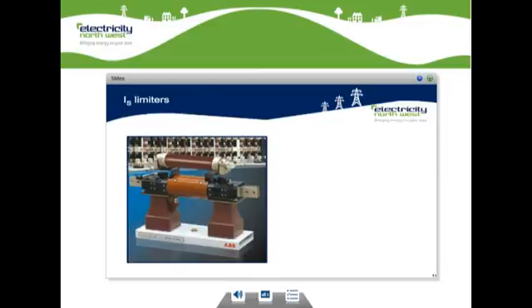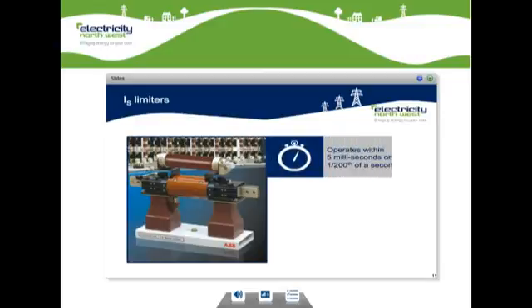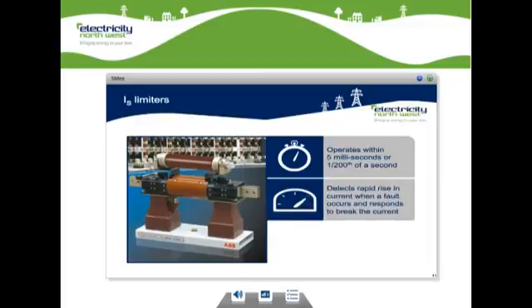Next, we'll cover the IS limiter. The IS limiter is a current limiting fuse. Now, our standard equipment will normally identify a fault and respond to it within a couple of hundred milliseconds. This might seem fast, but the fault current will have already peaked within this short time frame. An IS limiter, however, will operate within 5 milliseconds, or 1/200th of a second, before the fault current reaches its peak. When enabled by the Fault Level Assessment Tool, the limiter will monitor the normal current flowing through it. When a fault occurs, the limiter detects the rapid rise in current and responds by setting off a small explosive charge, which breaks or diverts the normal flow of current to a fuse, where it is extinguished.